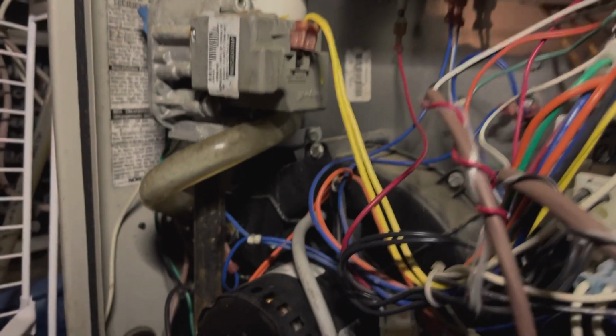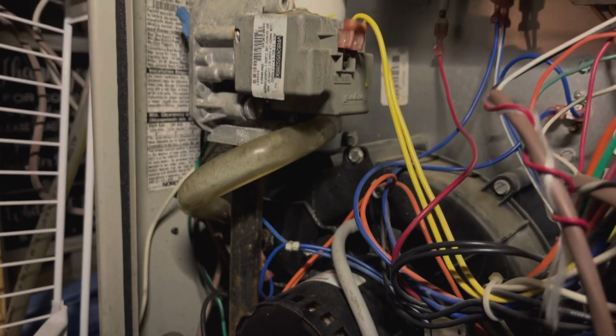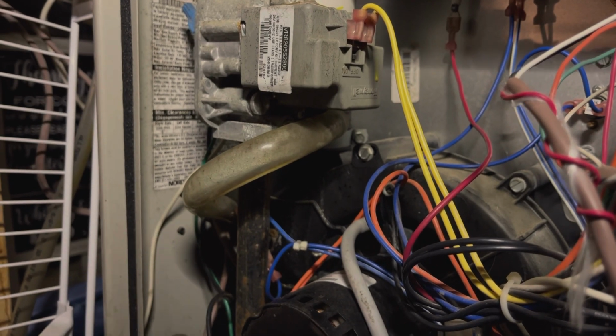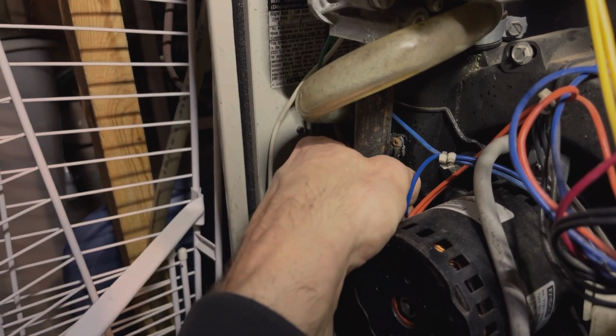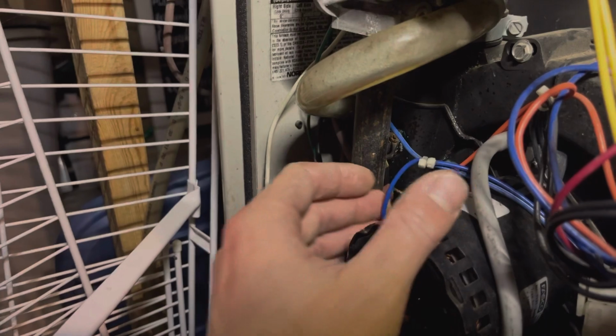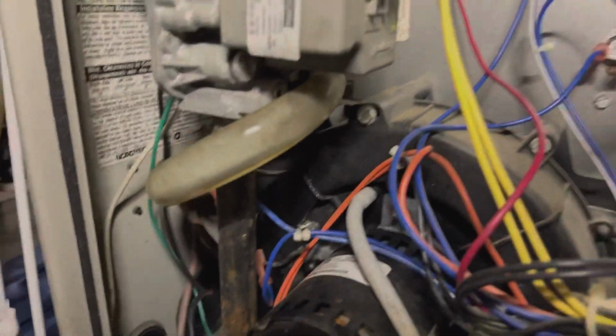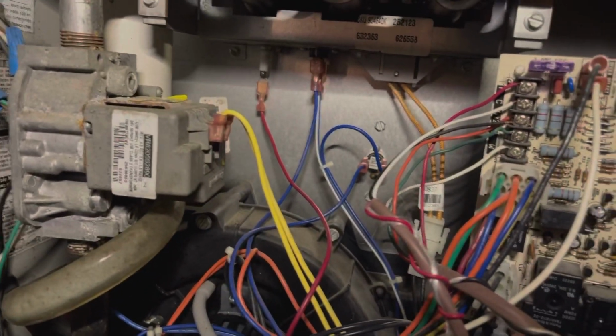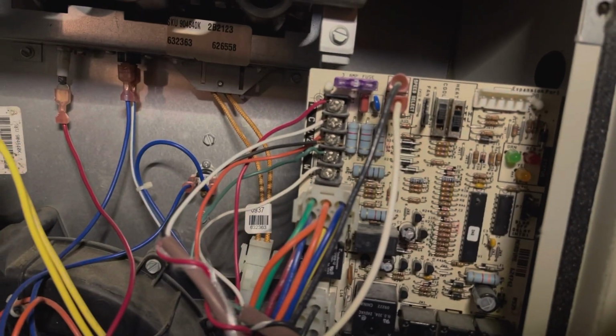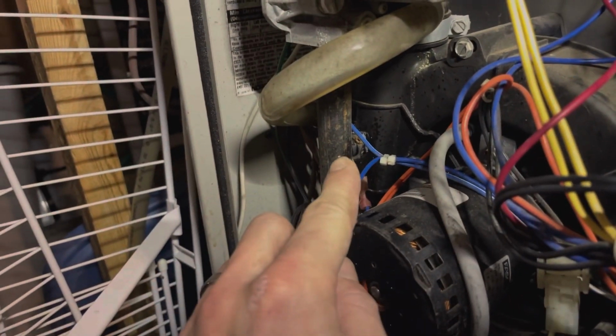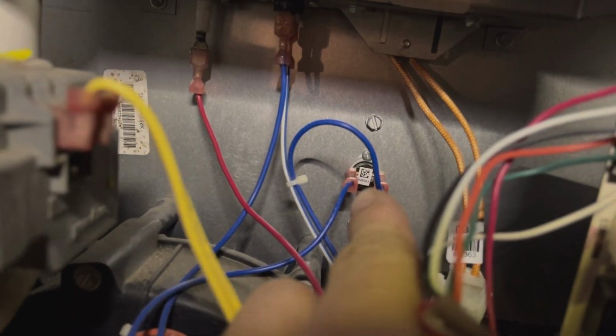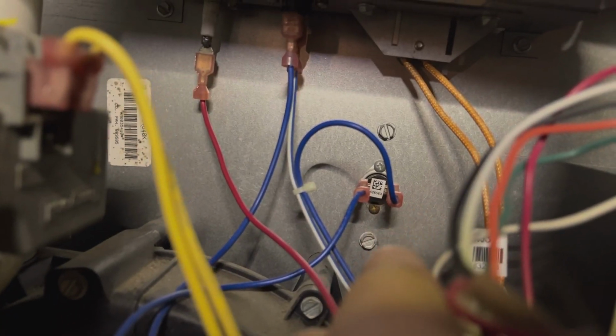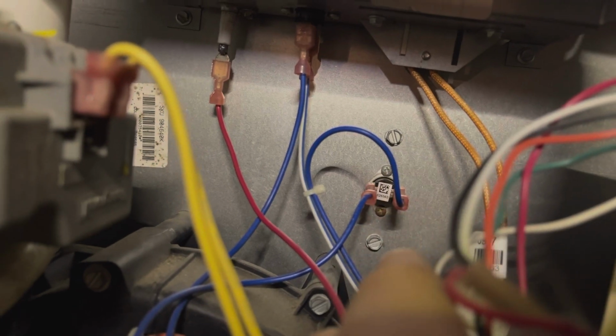I'm going to try and unplug one of my limit switches and show you what fault condition could arise. I'm just going to unplug this wire from this limit switch here. That's going to break the circuit, and it's going to give me a fault code so that we can see how that works. Now, while we're at it, you've got a limit switch here on the inducer motor. You've got a limit switch here on the side, and that one is for the air going past.